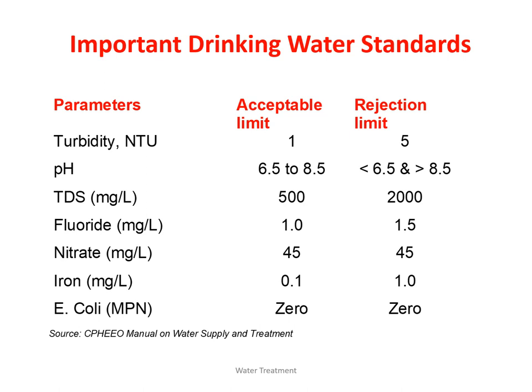Turbidity: the desirable limit is 1 NTU and the permissible limit is 5 NTU. pH should be 6.5 to 8.5 — if the pH value is less than 6.5 or greater than 8.5 it must be corrected; there is no deviation allowed in the permissible limit. Regarding TDS concentration, the acceptable or desirable limit is 500 mg per litre, and we can go up to 2000 mg per litre if no other water source is available.